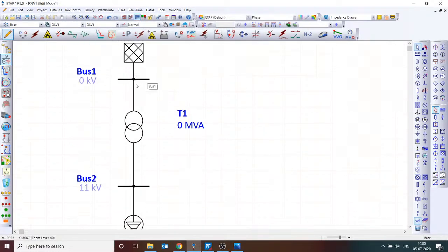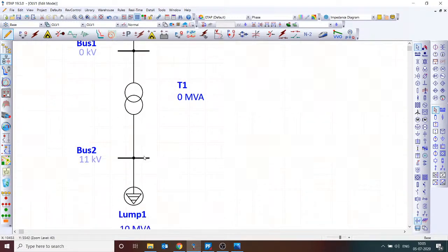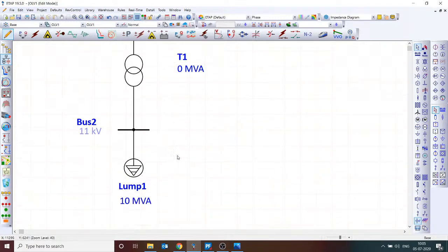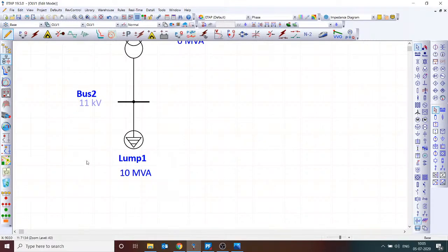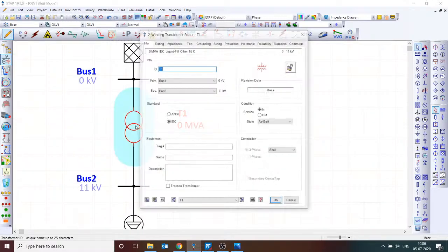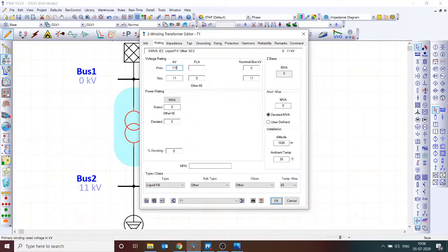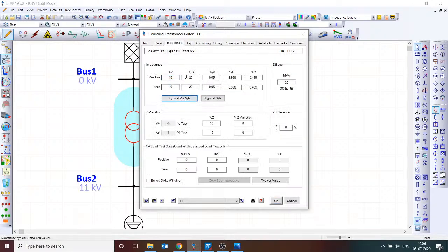The load is 10 MVA at 0.85 power factor, which is 8.5 MW. The transformer rating is, for example, 110/11 kV, 20 MVA. Assume the industry gets power supply at 110 kV. Regarding transformer impedance: typical impedance in ETAP comes from an old IEC 60076 standard, which is now obsolete. So when using typical Z and X/R in ETAP, please refer to the latest IEC 60076 Part 5 standard instead.